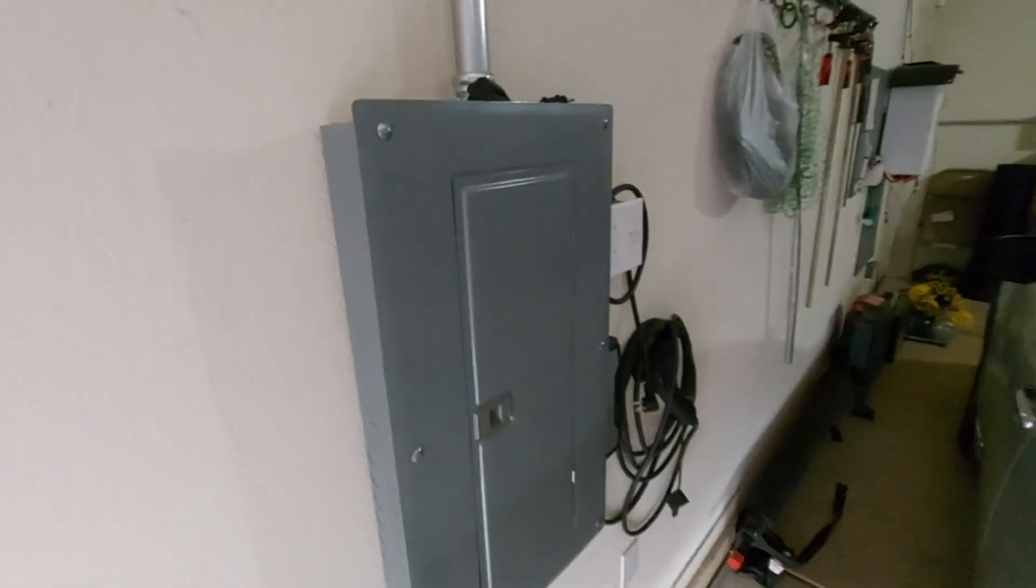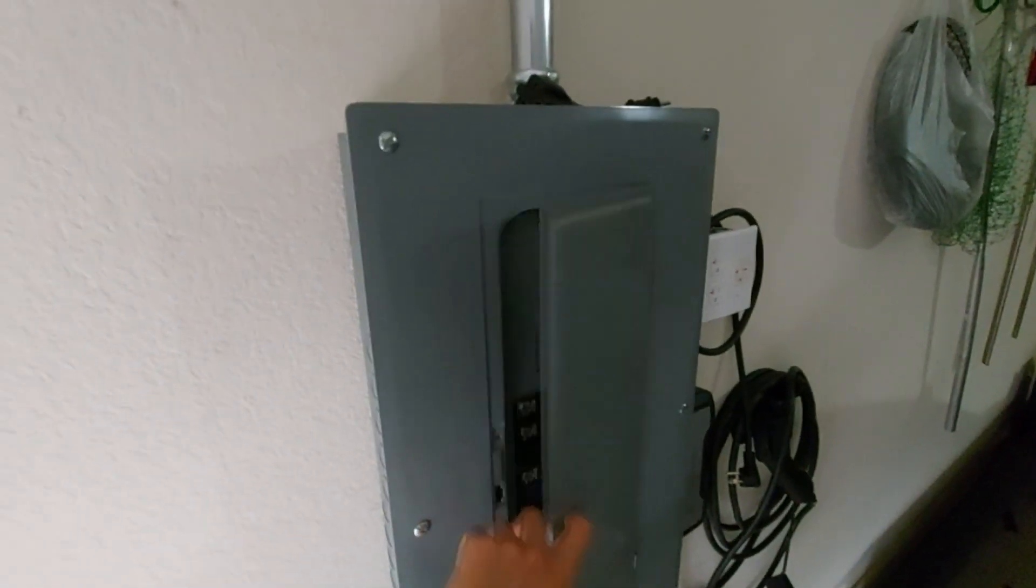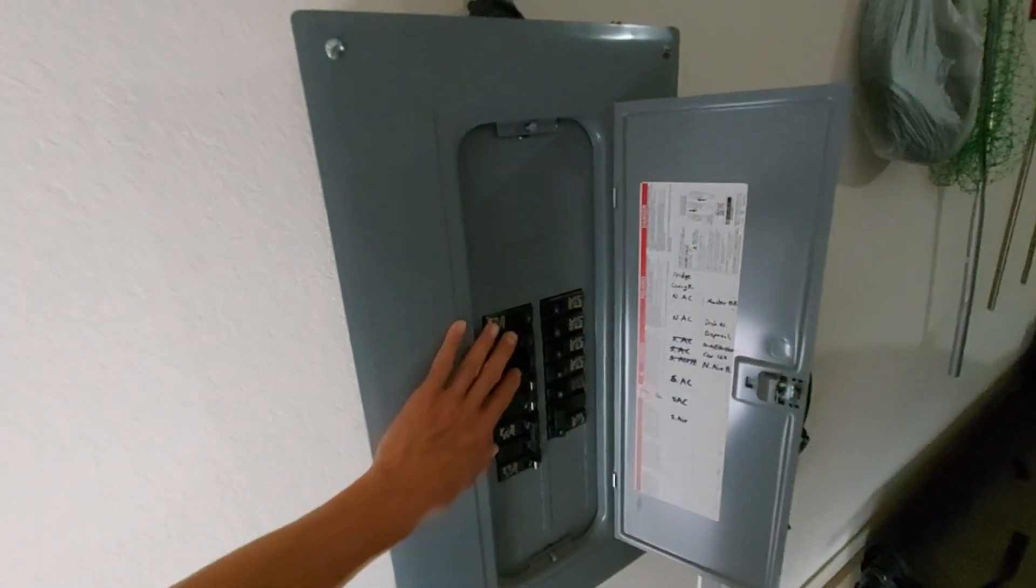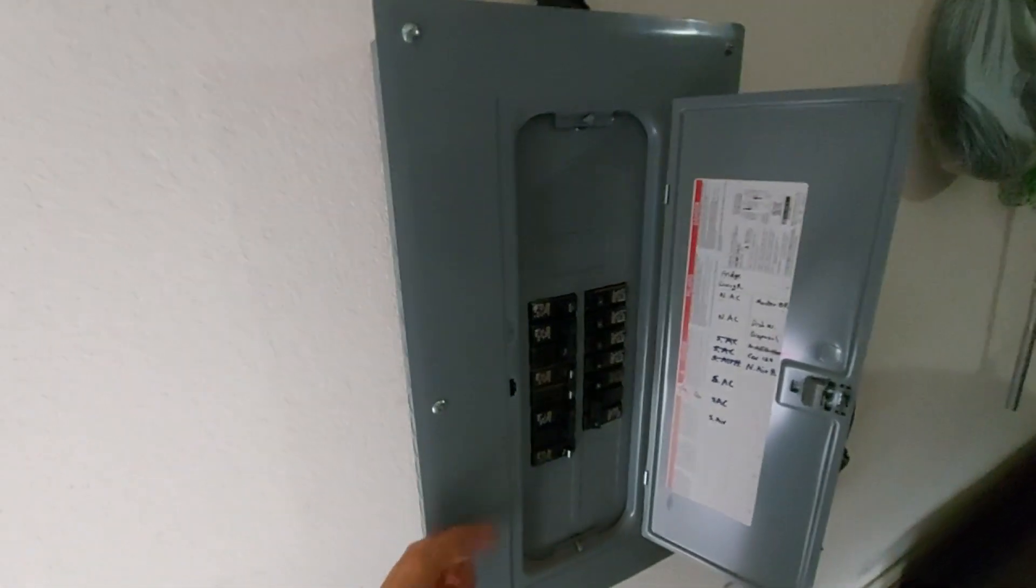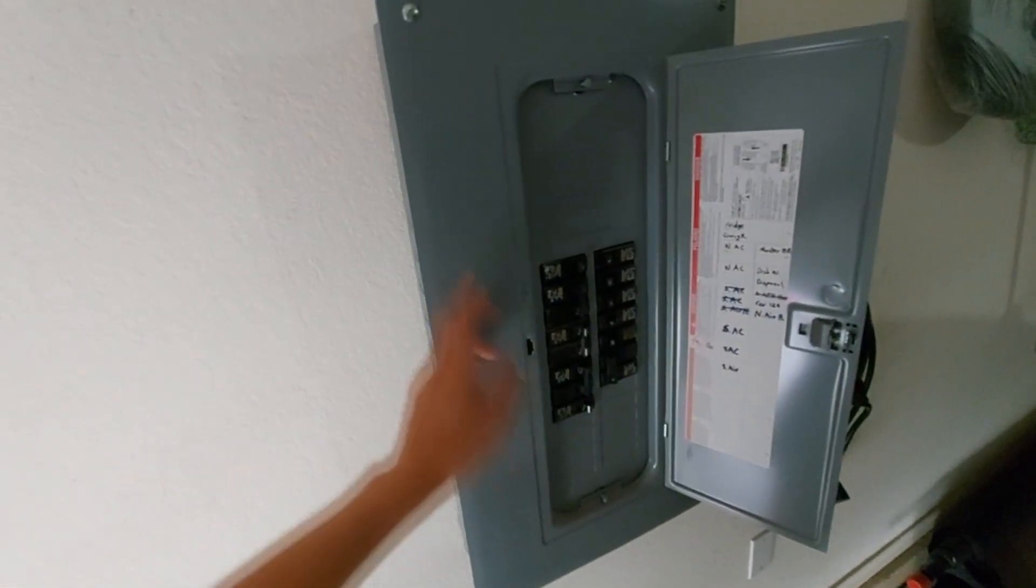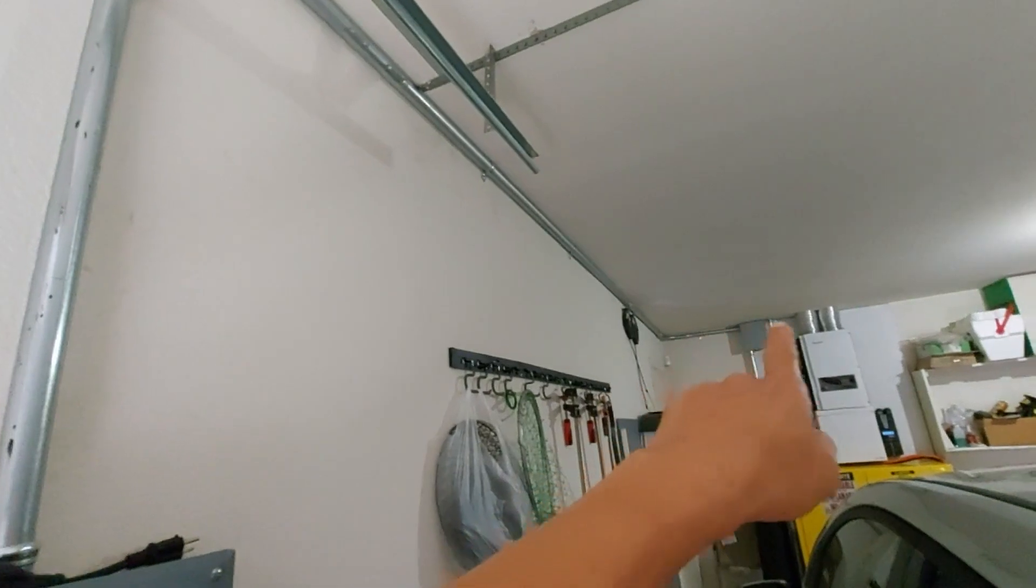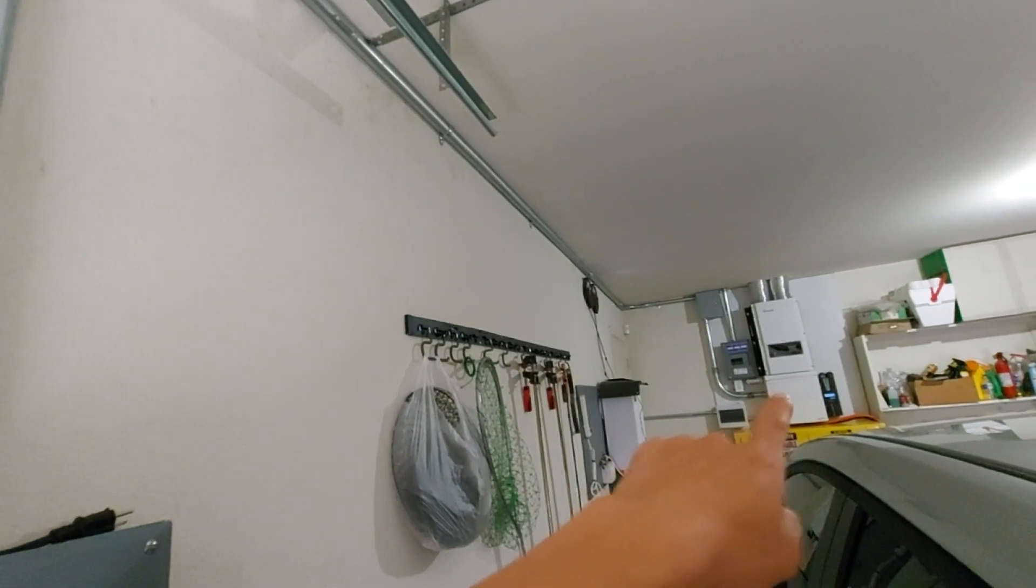So this is my sub panel. Because this is an off-grid system, I pulled all of the circuits that I want to use on my solar into all of these breakers and put it into this sub panel. Then I routed 60 amp, 240 volt split phase main line into this sub panel, and it goes straight here, goes into the pipe, and goes all the way down there, goes into the corner and right into the power distribution box into the inverter.